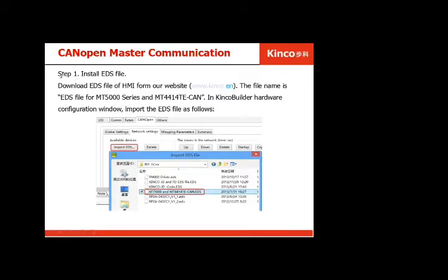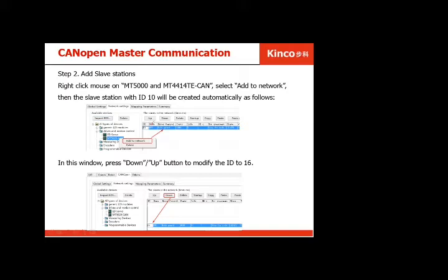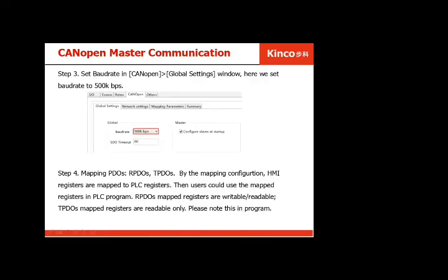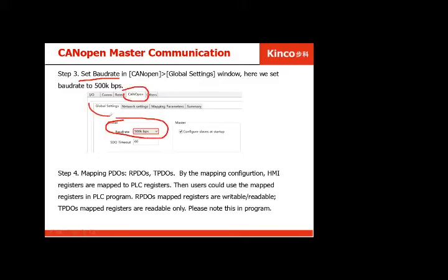The first step is to install the EDS file from our website. Then you add the slave station — double-click or right-click to add the network. You can press up and down to modify the node ID, which is the station number. Then set the baud rate for the CAN communication in the global settings. Setting 500 kbps is sufficient.